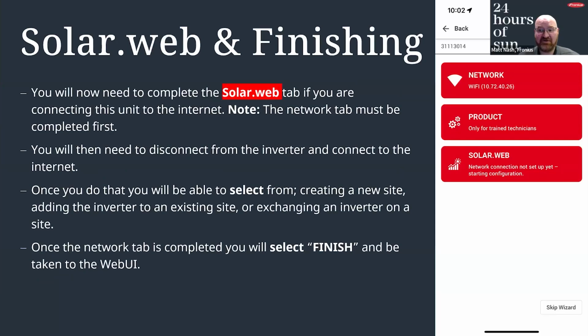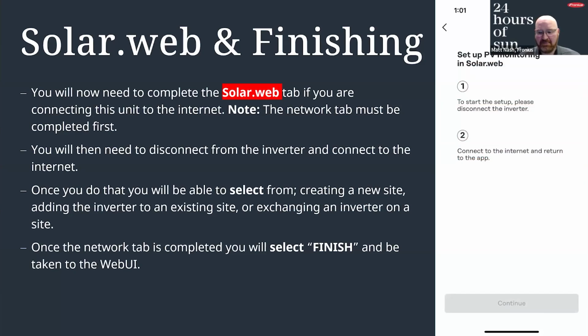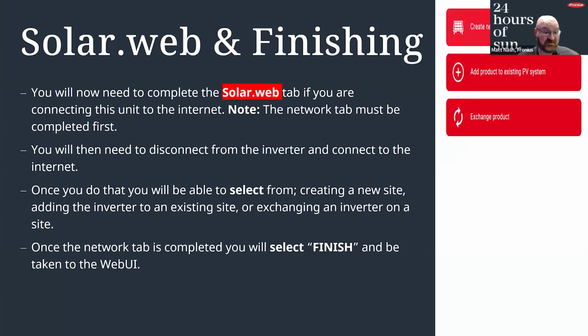The last portion is actually getting it on our SolarWeb monitoring portal. Of course, the network tab does need to be completed first. And what you'll do is you'll actually disconnect from the inverter and connect to the same network that the inverter is connected to. Once you click on the SolarWeb tab, then you're connected to the internet. You'll actually be able to create a new system, if this is a new installation. You can add a product to an existing system. If there's another inverter of ours that is connected, you can actually exchange out this particular inverter with the Gen24, and it'll do all of that for you.